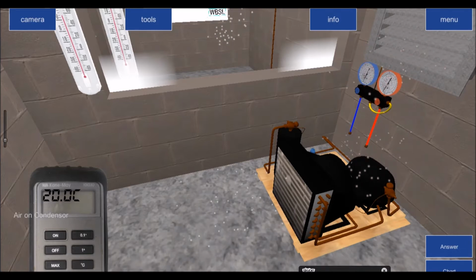With water cooled condensers, you can guarantee that the water is going to be constant even when you're using a water cooling tower, so you're kind of guaranteed a constant temperature. With air cooled, air temperatures fluctuate up and down. The warmer my air temperature, the higher my condensing pressure. The lower my air temperature, the lower my condensing pressure. But there will always be a difference of between 10 and 20 between whatever the temperature is of the air on and the refrigerant circulating inside the condenser, or in the heat rejection heat exchanger.